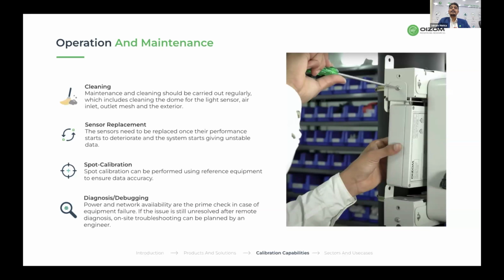Sensor replacements: the standard lifespan for dust sensors is 12 months in normal conditions, whereas 24 months for gases. This varies based on pollution concentration - the lifespan isn't the same in the desert of Saudi Arabia as in the pristine fields of Scotland. On average, dust sensors have a lifespan of 12 to 15 months, while gas sensors have a lifespan of 24 months.